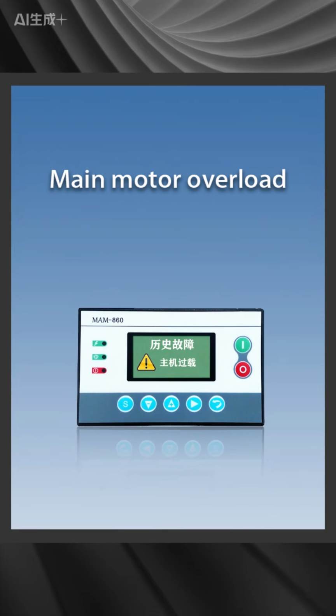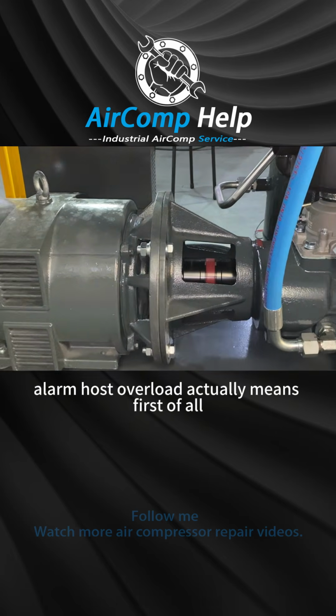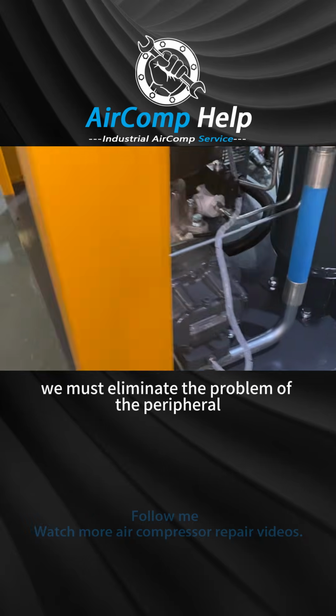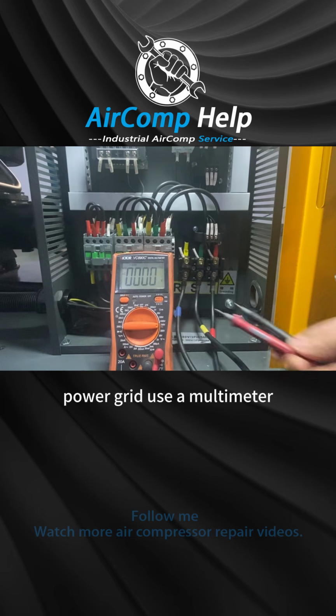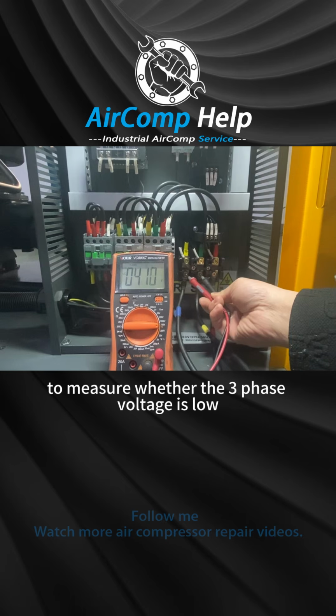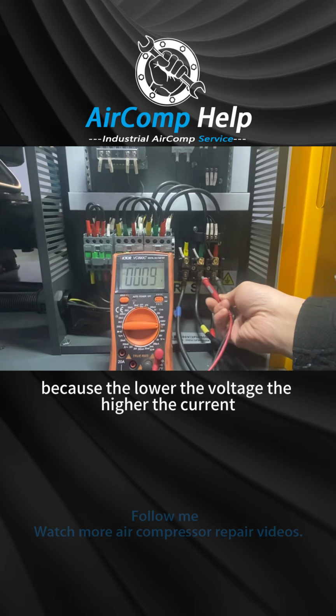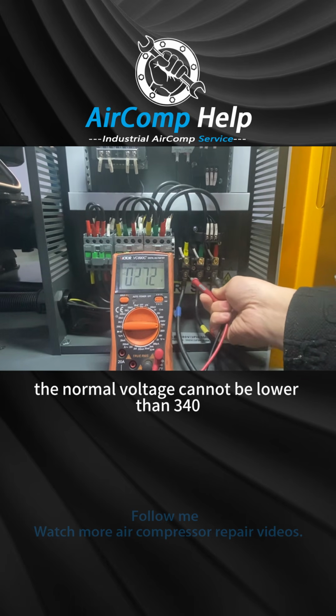How to solve the overload of the air compressor alarm host. Alarm host overload actually means, first of all, we must eliminate the problem of the peripheral power grid. Use a multimeter to measure whether the three-phase voltage is low, because the lower the voltage, the higher the current. The normal voltage cannot be lower than 340.